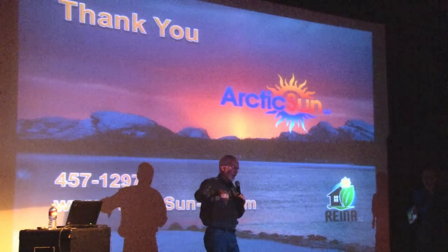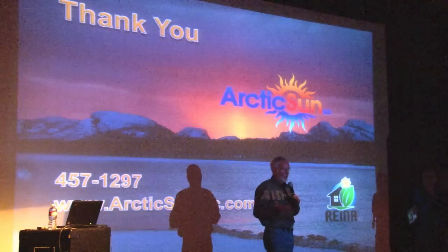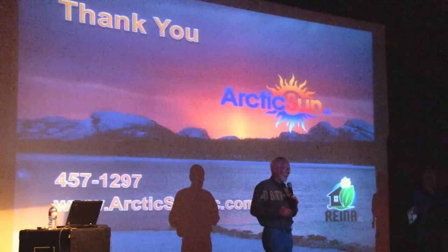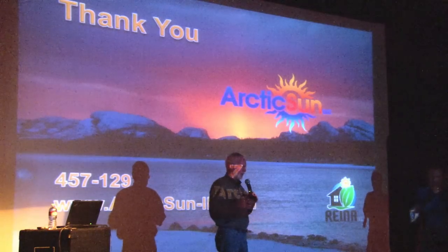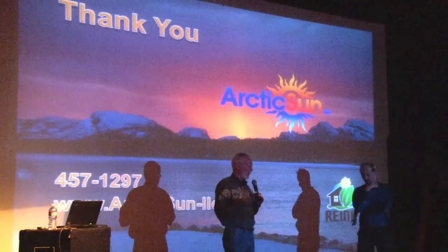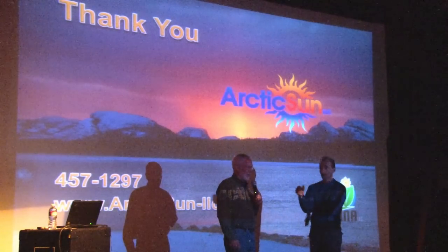And there's also PEX tubing through it. So if he has extra thermal energy from his thermal panels and he wants to boost that up a little bit, he can do it that way too. So it's kind of a twofold system. If you eliminate the PEX and just go with the sand, you can still use it. It's just a big thermal mass dump underneath the floor. The additional cost for a house to do something like that is maybe $500. You know, sand's cheap.